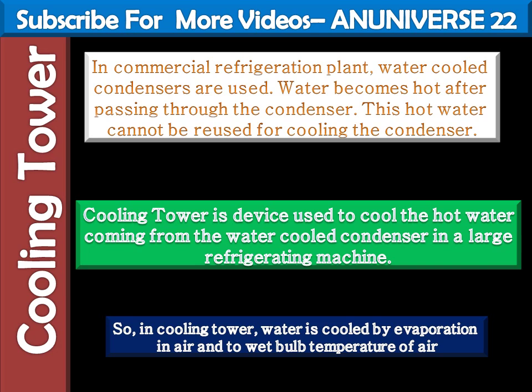An important point: the capacity of a cooling tower mainly depends upon the amount of water surface exposed to the air, the length of the exposure time, the velocity of air passing over the water droplets formed in the cooling tower, and the wet bulb temperature of the atmospheric air.